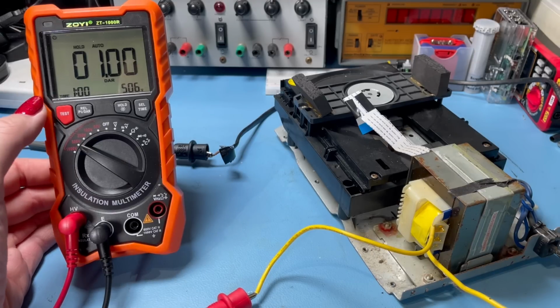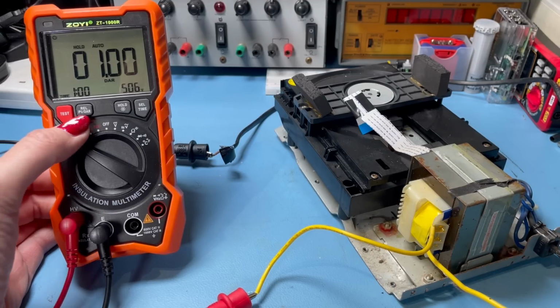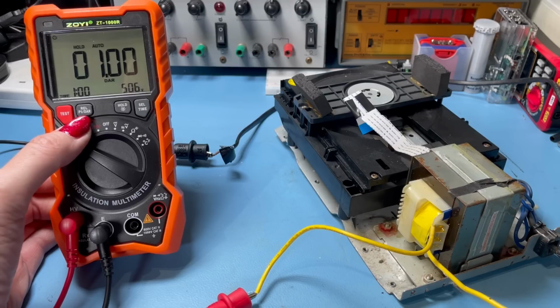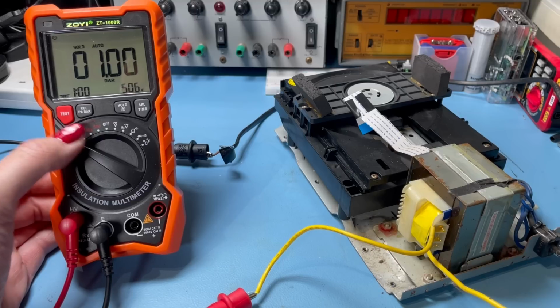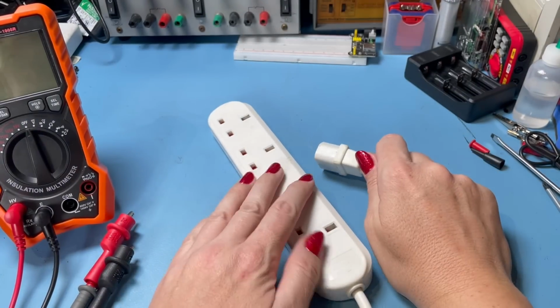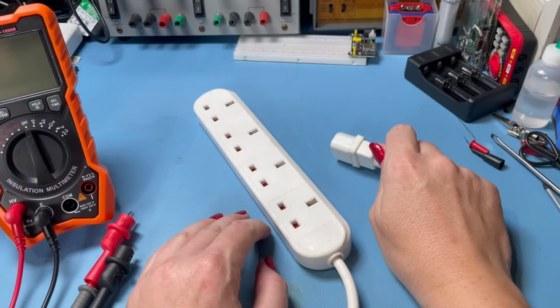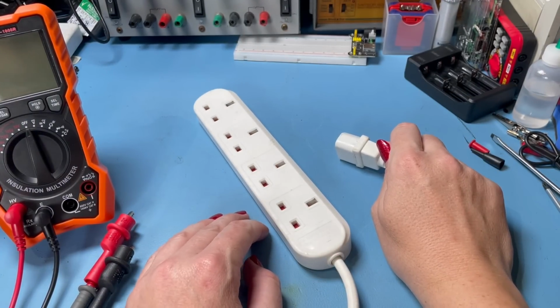If you're not sure that your reading is okay, you can always do a PI test. Now, the PI test is the same as the DAR, but it takes a little longer, and it compares the values at 1 minute and 10 minutes. Okay, so another thing you can use this to test, and I've tested an awful lot of over the years in PAT testing, is an extension lead.